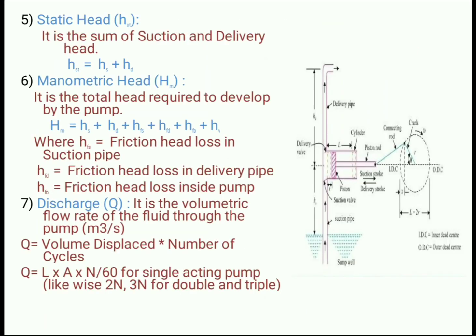Next terminology is static head. Static head is the summation of suction and the delivery head. So static head HST is equal to HS plus HD. Manometric head, it is the total head required to be developed by the pump. And manometric head is equal to what? Suction head plus delivery head plus HFS plus HFD plus HFO and HV.